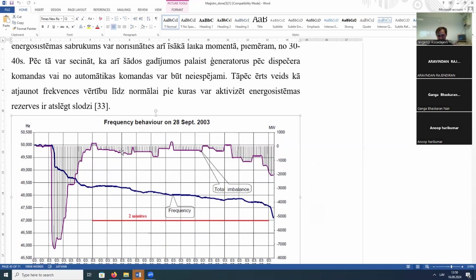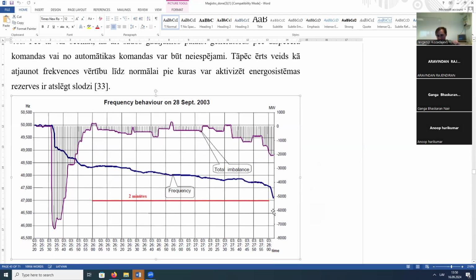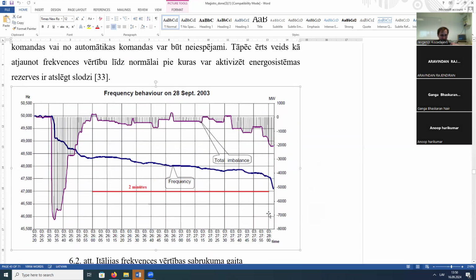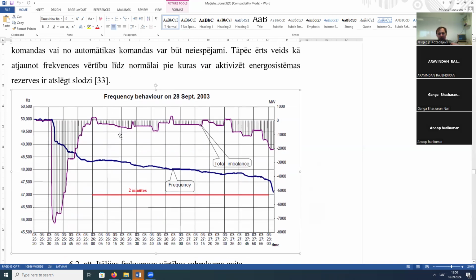But they have no under frequency automation to restore the frequency. They have only automation to restore the balance. And as a result, the blackout. That's why, from my point of view, this second option for under frequency automation, with frequency restoration in automatic mode, must be there. But this is the philosophy of how to design your power system protection.